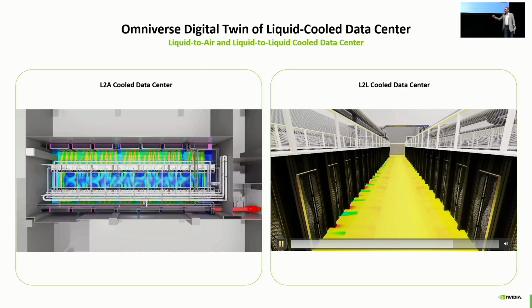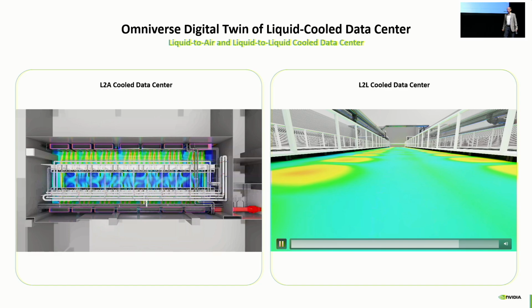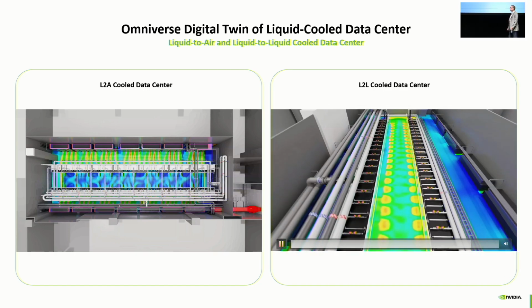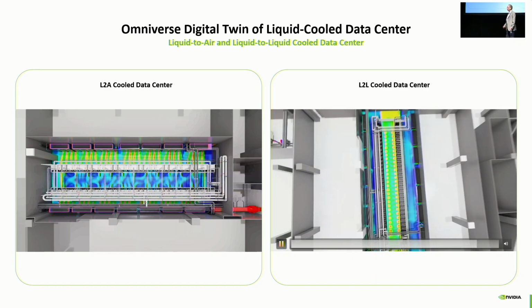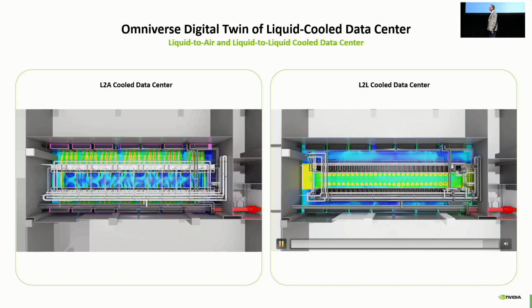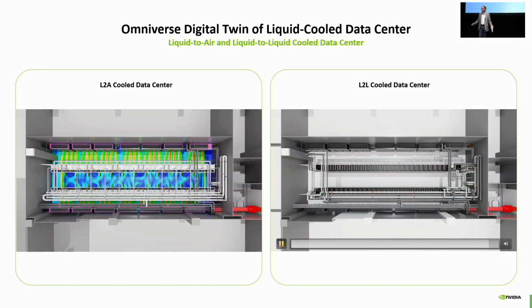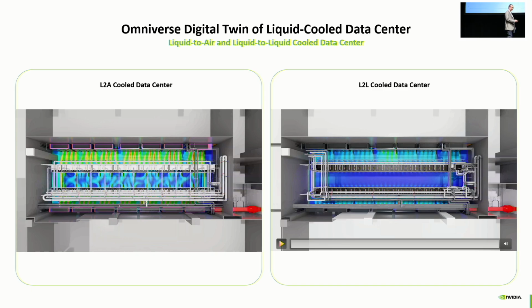So the CFD and the flow network modeling, I'm going to walk you through that, because these are tools we needed to generate, working with the industry, to be able to create this style of cooling. This shows very uniform heat removal, with the ability to handle up to 6 megawatts of heat generation within the racks, in very small space.